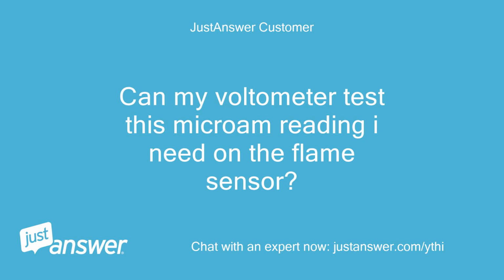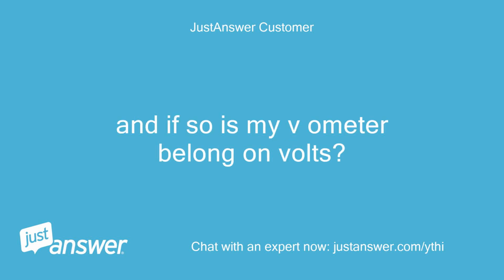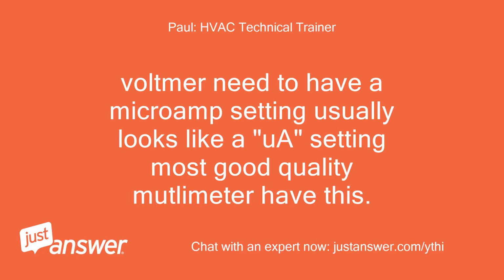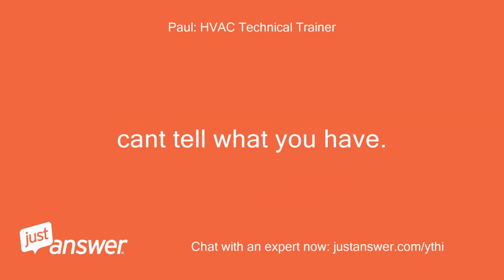Can my voltmeter test this microamp reading I need on the flame sensor? And if so, is my voltmeter on volts? The voltmeter needs to have a microamp setting, usually looks like a uA setting. Most good quality multimeters have this. Can't tell what you have.